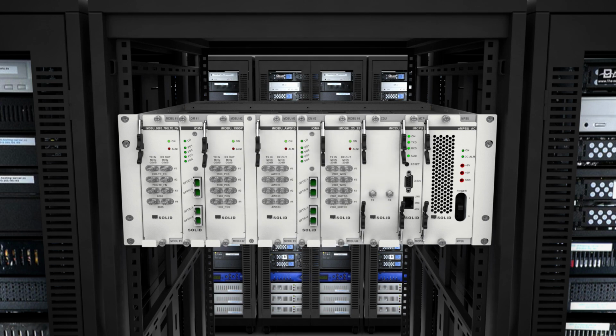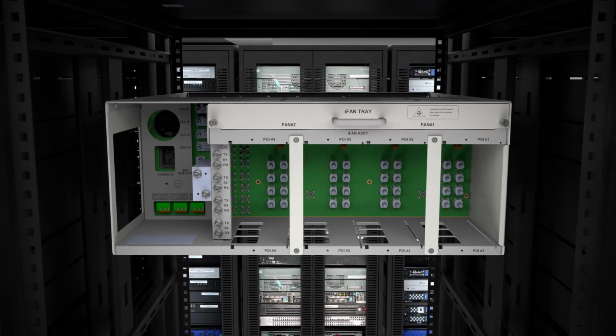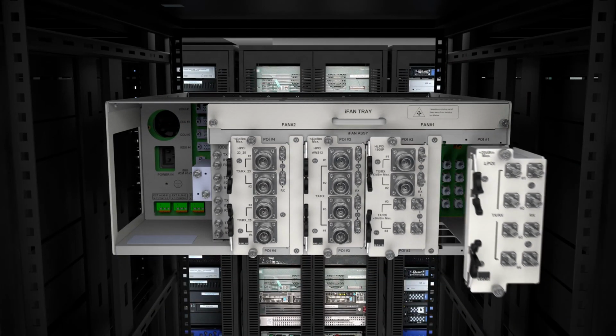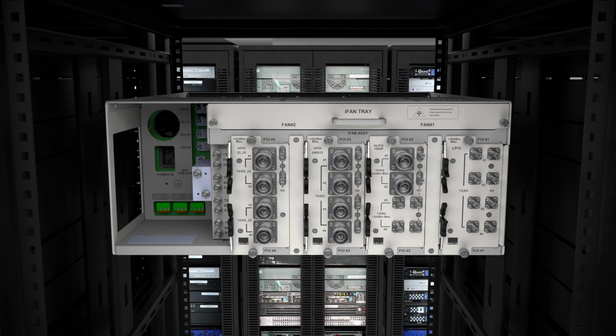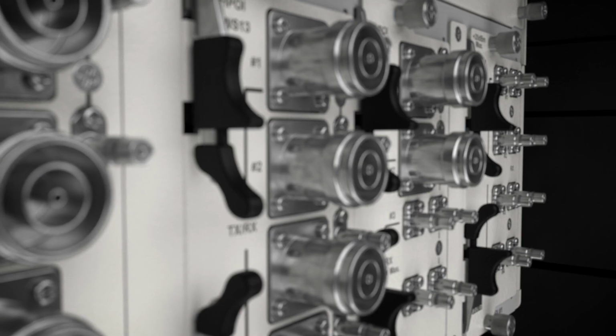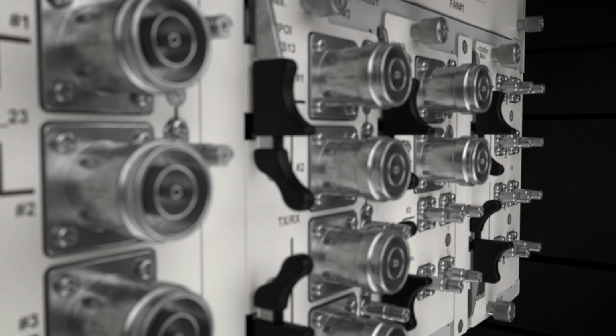Each IMDBU supports 1 or 2 cellular frequency bands. These cards provide filtering, leveling, and power control. On the back of the iBIU, POI cards interface with the IMDBUs. Each of the POIs support up to 4 services from the mobile networks. The POIs condition the radio frequency signals to appropriate levels for conversion to optical signals.